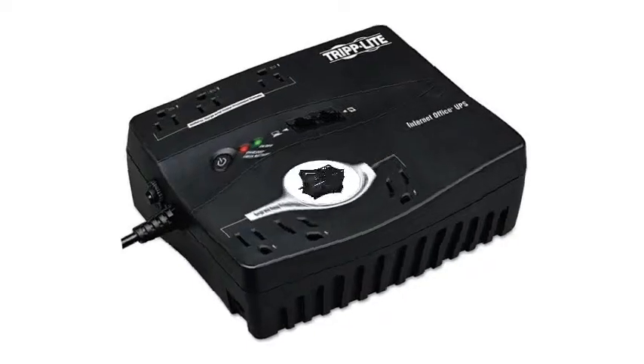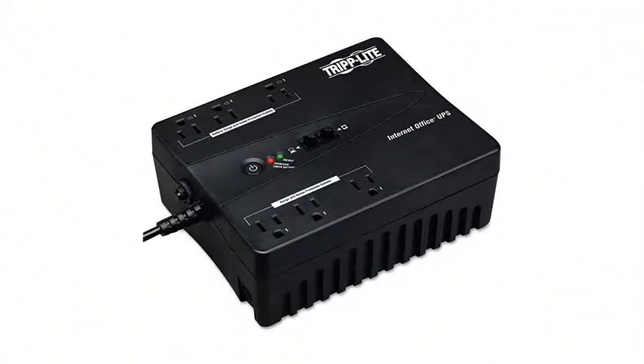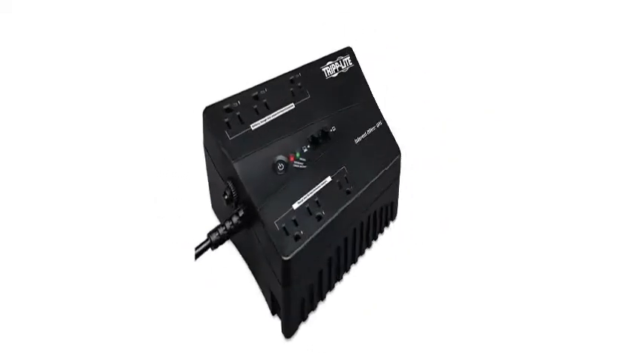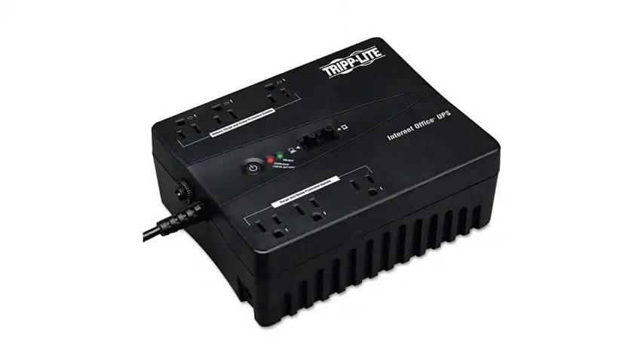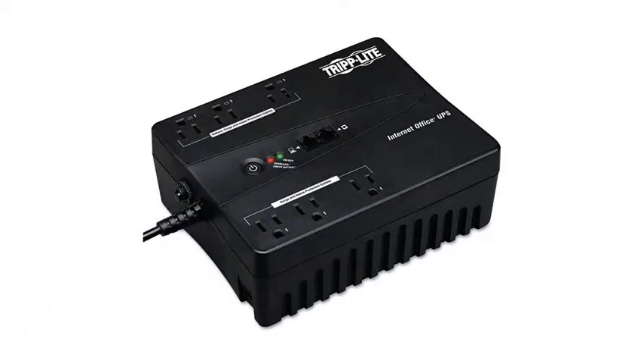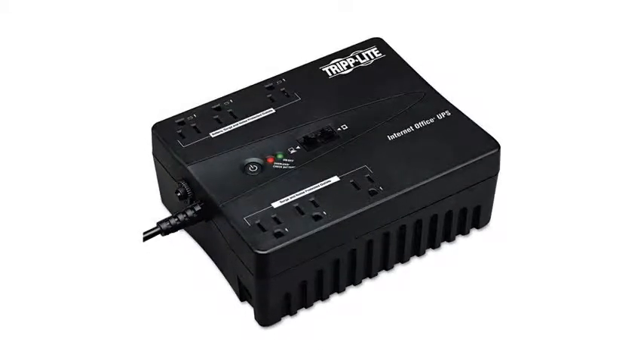With an output capacity of 350 volt amps and 180 watts, it has the minimum power necessary for a typical microcomputer. The output capacity is insufficient for a gaming PC. If you were taught that watts equals volts x amps, the formula does not apply to computer products. Although products such as incandescent light bulbs have equivalent watts and volt amps, computer equipment has watt ratings that are about 60% of the volt amps. Battery backups designed to protect computers follow the same power factor ratios as computers in order to have matching loads. Watts refer to the power bought from the utility company. Volt amps are the unit of measurement used to correctly size wiring and circuit breakers.